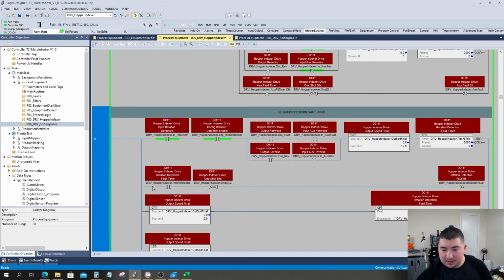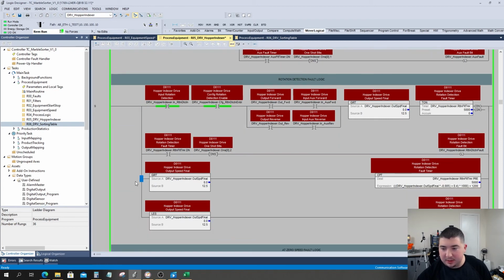And one last thing also, an additional thing that I added to the motor logic was a smarter calculation for determining our rotation detection alarm timer. So what this is, if our speed is greater than 12.5, and I calculated this as being the minimum speed at 12 volts, or 2 volts from the output, because if you remember, the drive will not respond to any value less than 2 volts. So I calculated that on the calculator. 2 volts would be 12.5, so our minimum speed would be that. As long as our minimum speed is greater than 12.5, we will calculate a new preset.